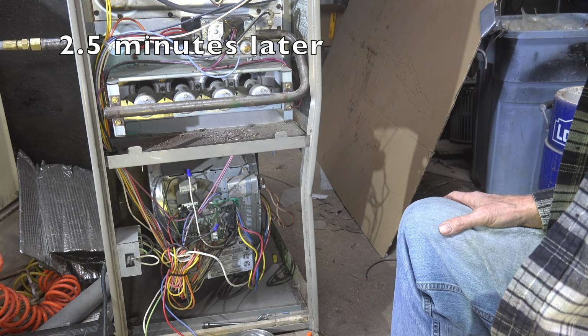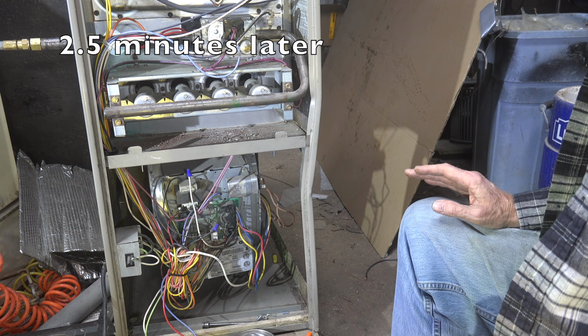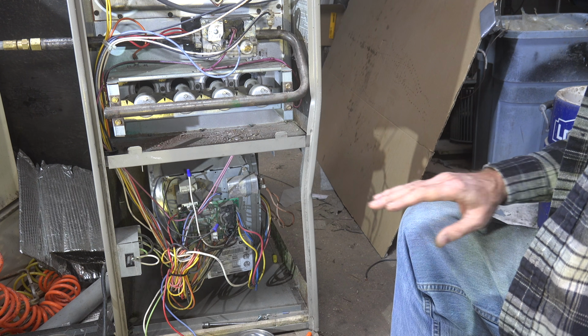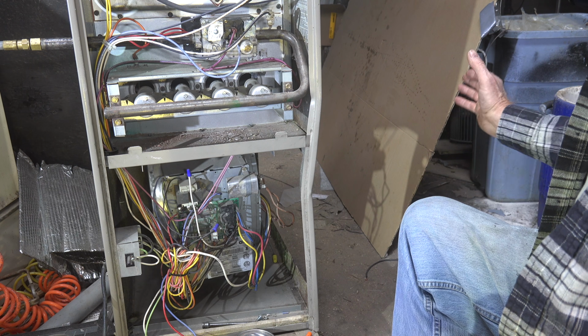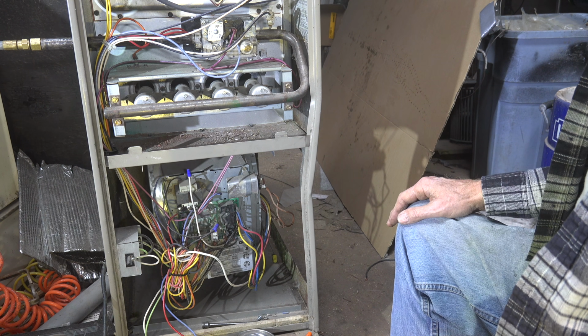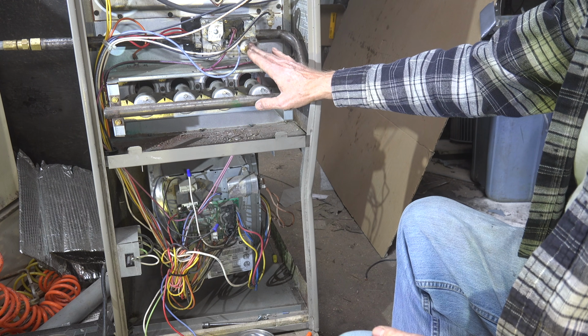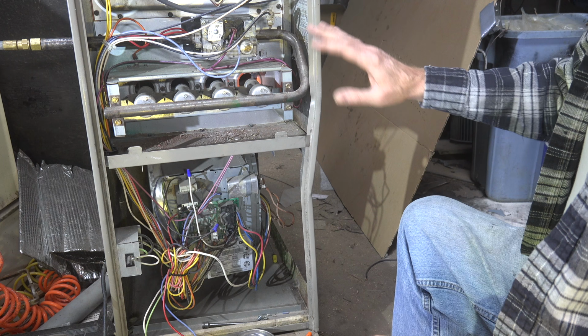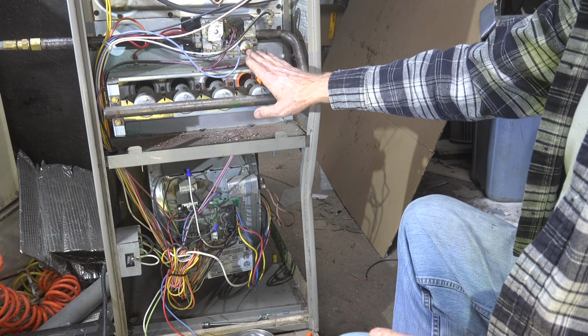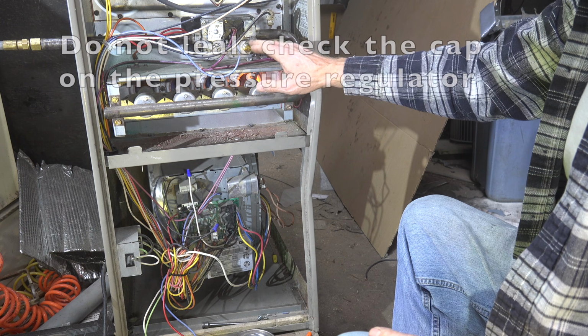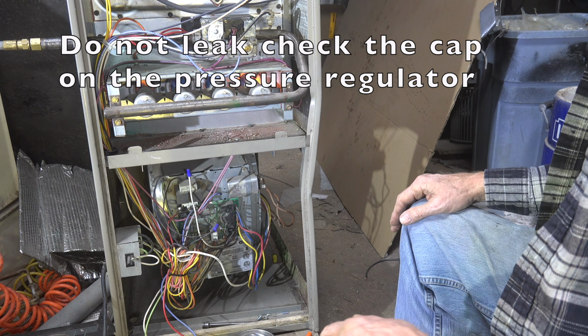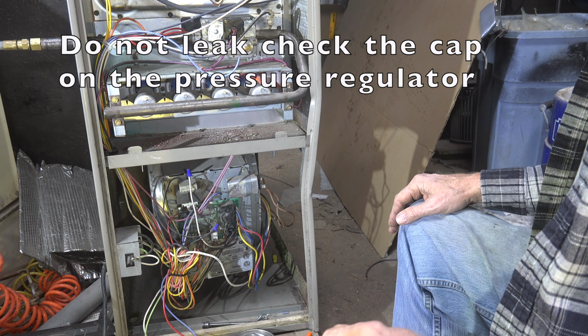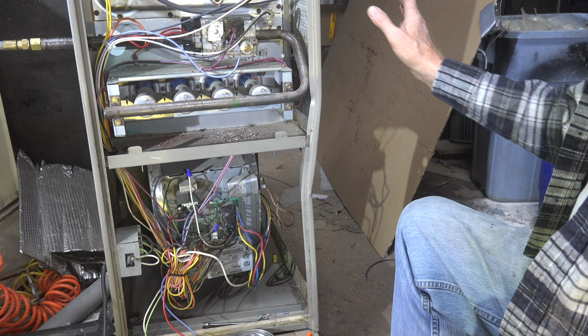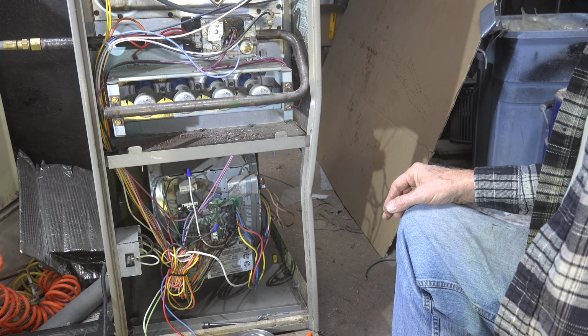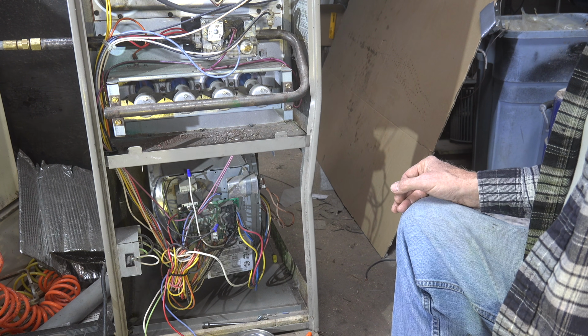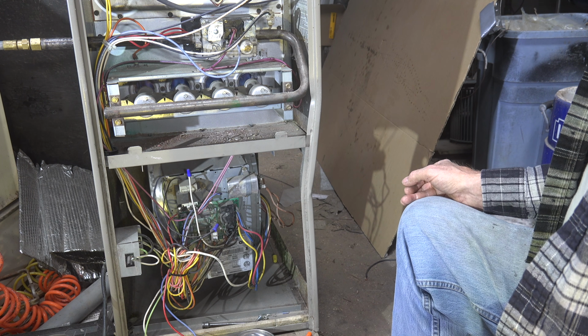Okay, so the burner's shut off. You can reconnect your fan switch with the power off again and fire the machine up and make sure it runs normally. You've checked your limit at that point. You've checked your manifold input. Once you're all done, check every place that you've disturbed here. Don't bother checking here. That's not going to help. Let's try it again. So the limit has kicked off and it's fired off. Anyway, that's how to change a heat exchanger in the GMP Goodman furnace. That's it on this one.